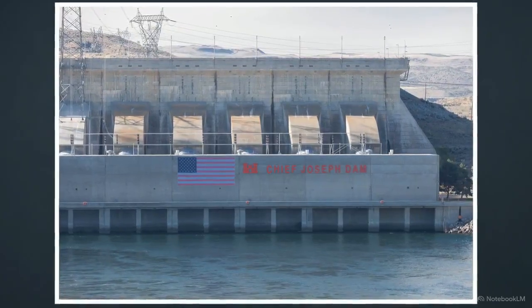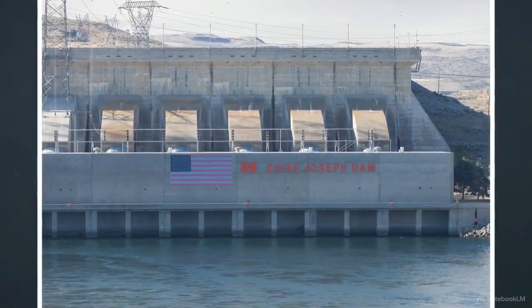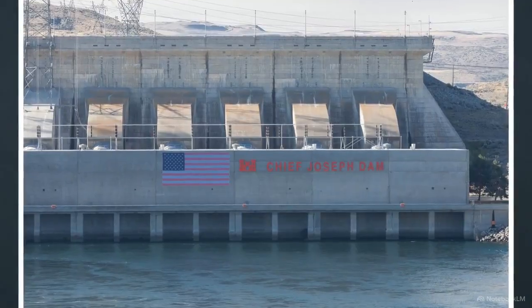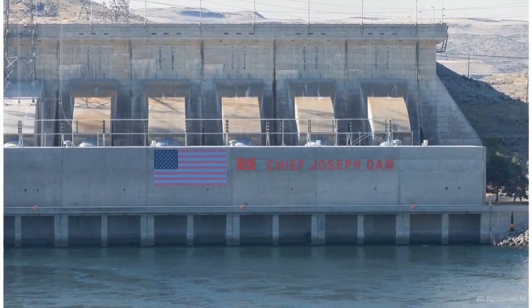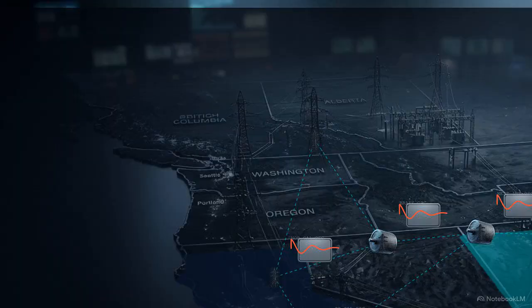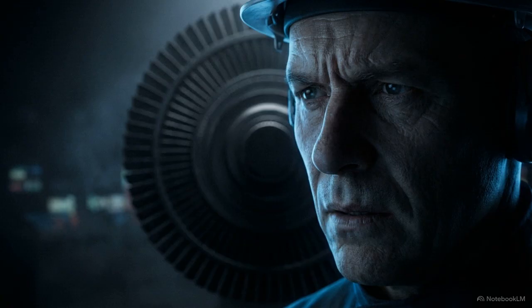At the Chief Joseph Dam in Washington state, operators conduct these tests using a massive 1,200 megawatt dynamic braking resistor. By slamming this colossal load into the grid for just half a second, they deliberately ping the entire western interconnection, revealing the exact shape and frequency of the resulting oscillations. But these physical field tests exposed a critical flaw in how we monitor the grid.